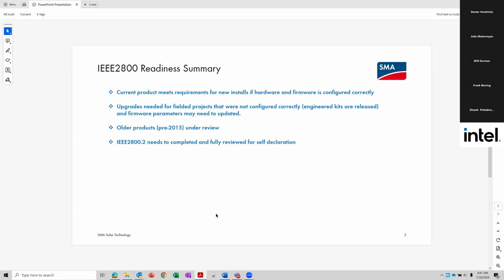We are 4 generations into our inverter products in the US, and our pre-2015 products, which is the CP series of products, that is under review in R&D. But post 2015, our megawatt sized inverters can all meet IEEE 2800 requirements. And the way we intend to comply is through a self-declaration for IEEE 2800 until such time that the test standard being developed in IEEE 2800.2 is fully completed.